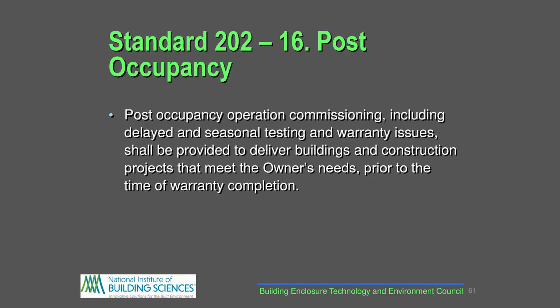Prior to that, in the post-occupancy phase, you want to take a look at the building before the end of the warranty period, whether it's the contractor's guarantee of 1 or 2 years, or the system warranty. Typically this is the 10-month warranty LEED requires, or a 23-month inspection. Whatever that guarantee period is, you want to check the building is still performing as it should and addressing the owner's needs before the warranties expire, because that's the opportunity to get contractors back to address issues without necessarily additional cost to the owner.